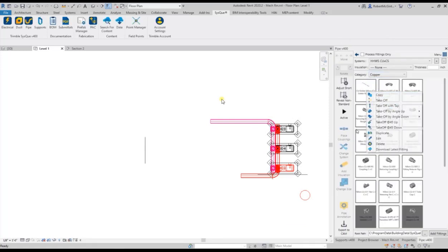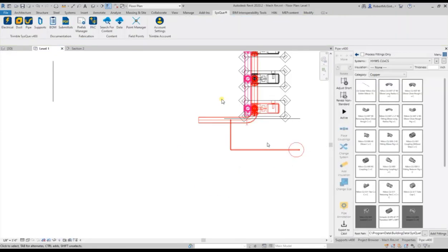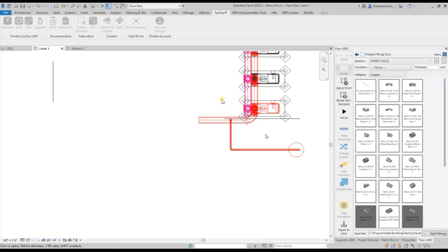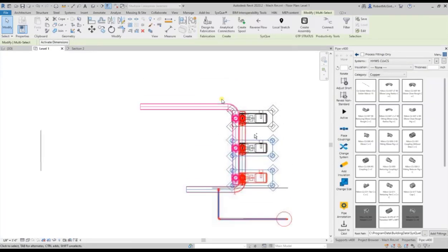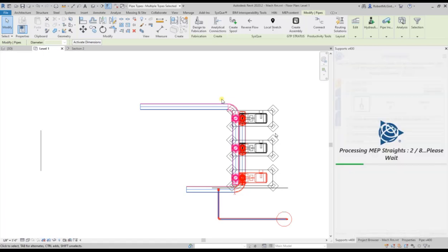I use it for hangers. Anything I touch in Revit, I have a SysQue palette for. I build a lot of my palettes before I start the jobs with fittings, families, everything like that, so that when I'm in a job, I know that there's no questions to be asked about what's in there. I know everything's in there. Another unique tool about SysQue is their hanger. You're able to click the pipe and click a button, and your hangers are automatically placed. You can set your hangers a foot to 6 inches off of fittings. There's so much you can do with that aspect of it.